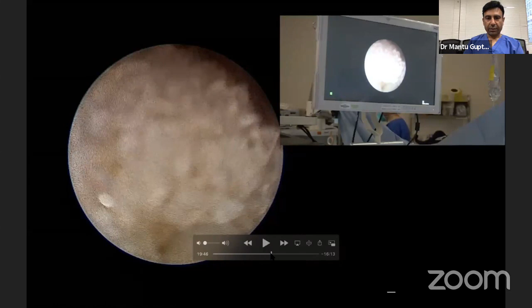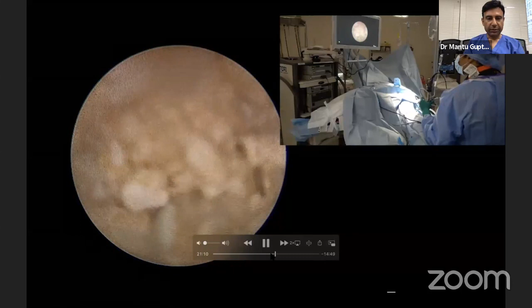And here's our Trilogy probe. It's a 1.5 millimeter probe. This probe I usually use at a frequency of 8 hertz, 100% suction and 100% ultrasound energy. And you can see it very rapidly breaks the stone and suctions it at the same time. Some people say, well, can you get any fragments out of a 1.5 millimeter probe? Actually it suctions very well, and it's got a collection bottle, so the pieces get collected toward the end. The nice thing about having the clear Petra in this sheath is that any smaller particles that don't get suctioned out with the ultrasound go through the sheath. You can see here very rapidly, we can break this stone up.